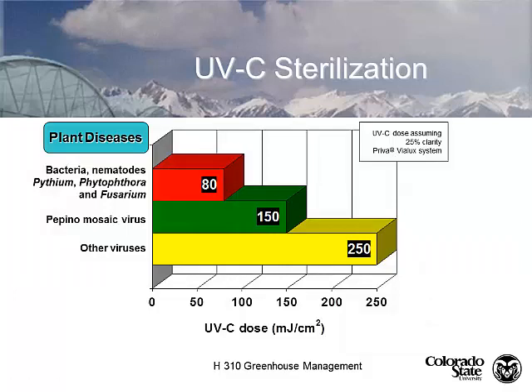We generate UVC radiation in a lamp and use it as a sterilizer. A UVC dose of 80 mJ/cm² is enough energy to kill most bacteria, nematodes, Pythium, Phytophthora, Fusarium, and similar diseases — even in somewhat turbid water with about 25% clarity. For Pepino Mosaic Virus it takes twice as much, and for other viruses it takes 250 mJ/cm², which is a pretty lethal dose.